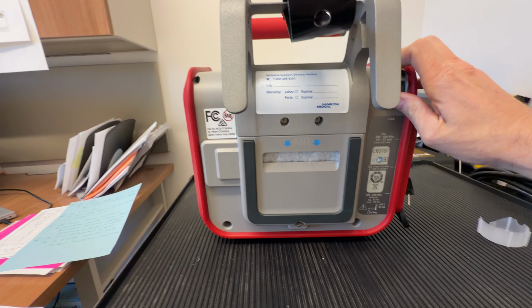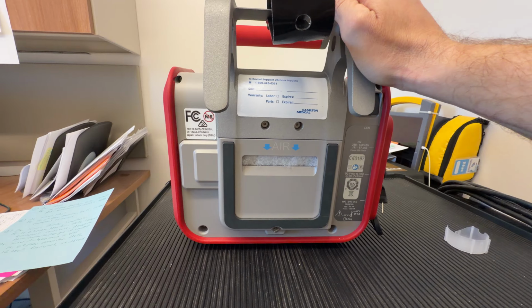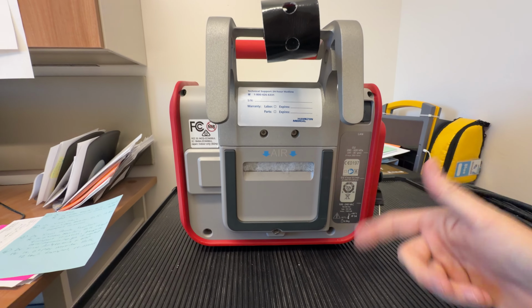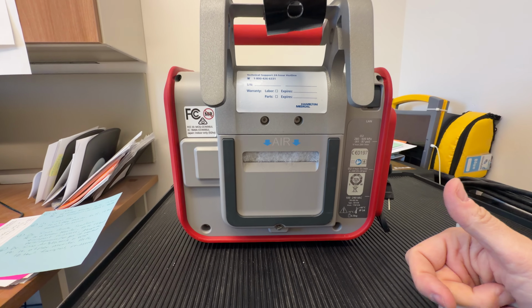And then this is your air inlet filter. This is the air that comes in that the turbine of the ventilator uses to create pressure, and then it'll mix atmospheric air, if you will, with the oxygen, either the high flow or the low flow oxygen coming in to produce the desired FiO2 that you set. If you don't have any oxygen going into the ventilator, it will still function as a room air ventilator, so that turbine is capable of producing all of the pressure and flow that you would need. It would only produce it at an FiO2 of 0.21.